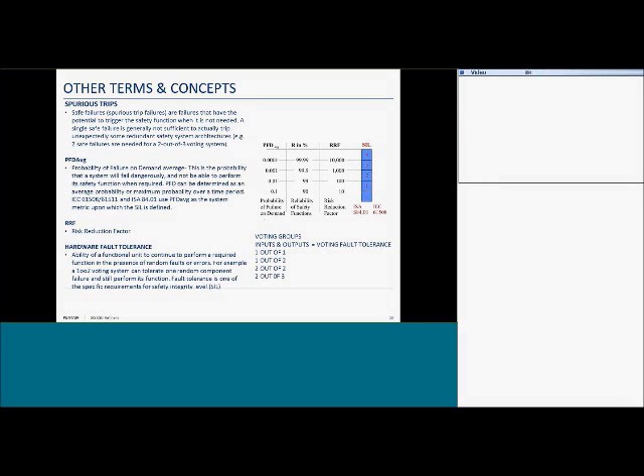So when you start to combine all these, obviously, if you have a product that has a better PFD average number than another product, that will directly impact your risk reduction factor. There are some other things that impact the risk reduction factor that are part of the design criteria, like hardware fault tolerance. You see that at the bottom of the page here.